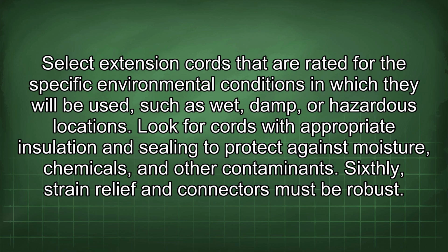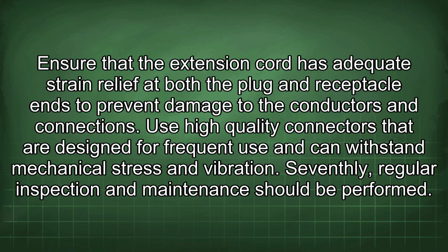Sixthly, strain relief and connectors must be robust. Ensure that the extension cord has adequate strain relief at both the plug and receptacle ends to prevent damage to the conductors and connections. Use high-quality connectors that are designed for frequent use and can withstand mechanical stress and vibration.